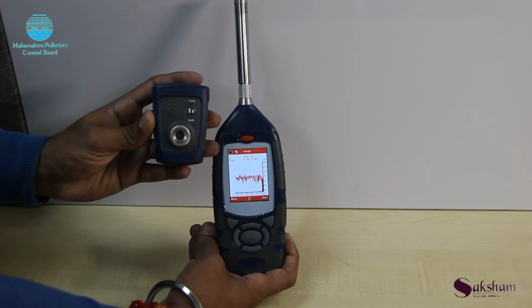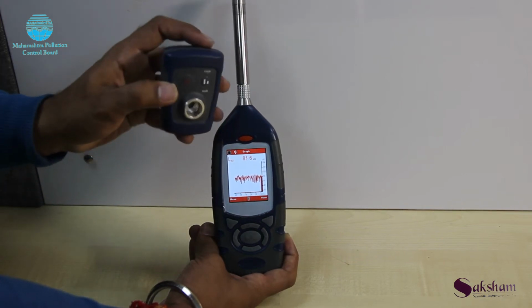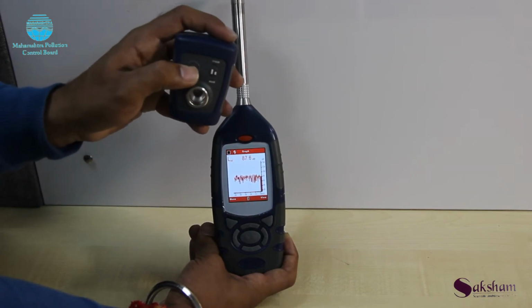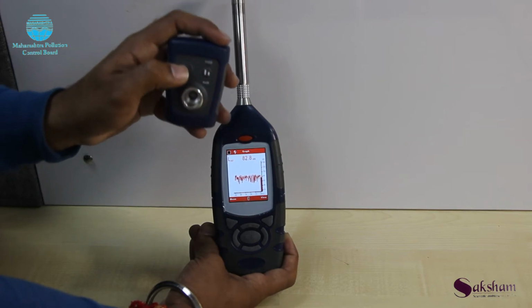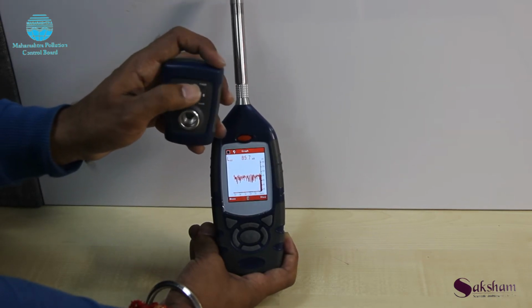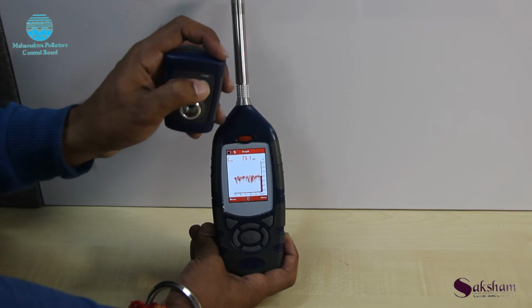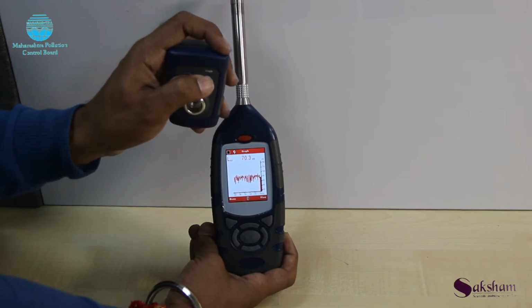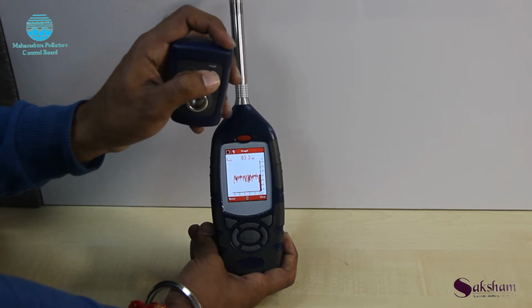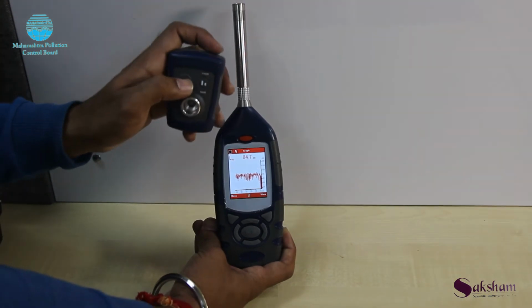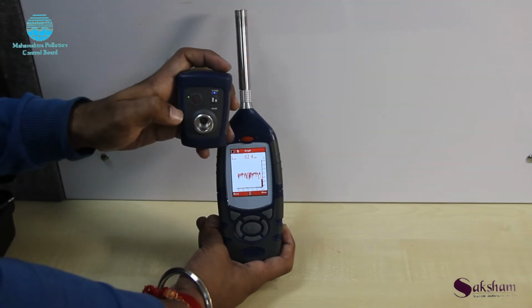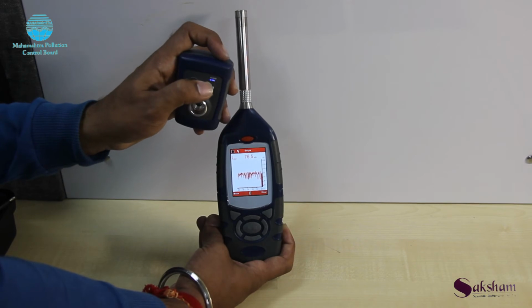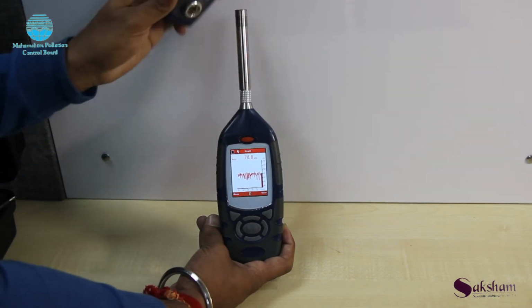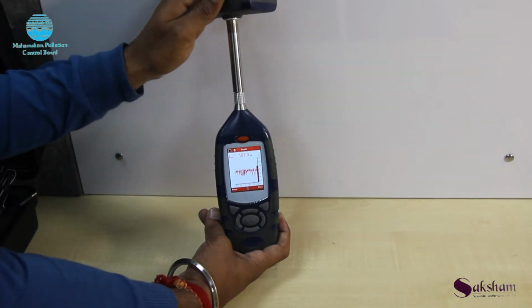So this is the acoustic calibrator. On this acoustic calibrator, this power button is there. As soon as I power on the sound level meter acoustic calibrator, it will blink the 114 decibel blue color light. See, I powered on, so this is the 114 decibel light.